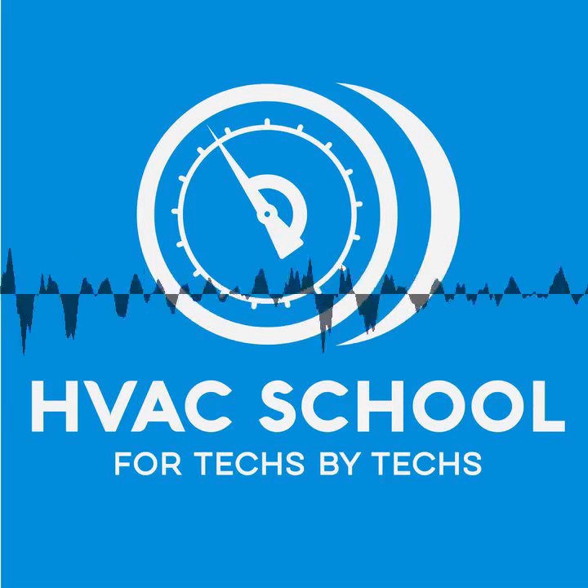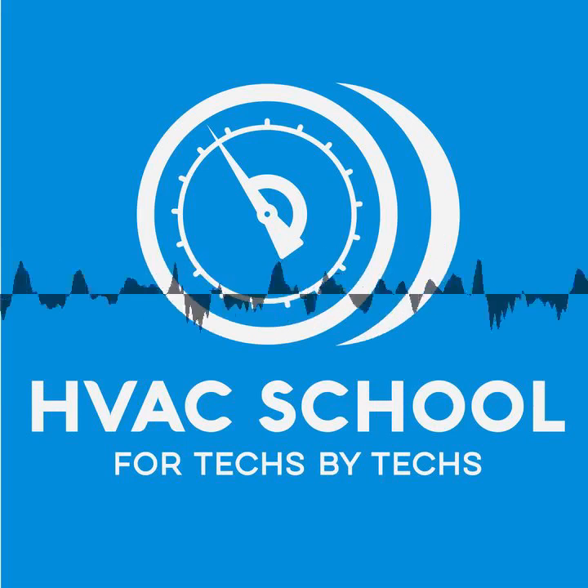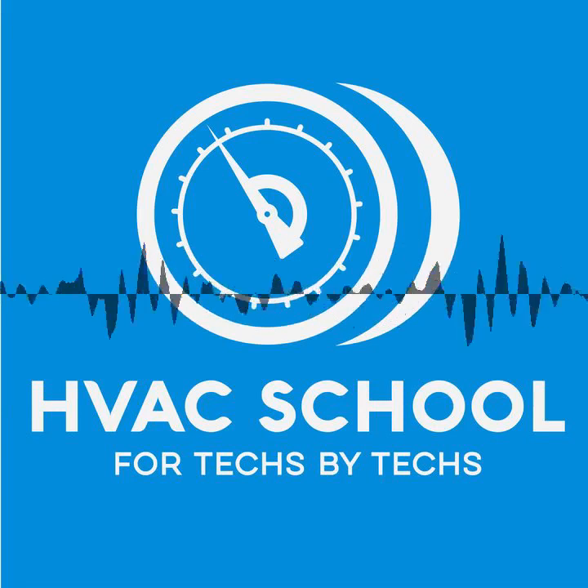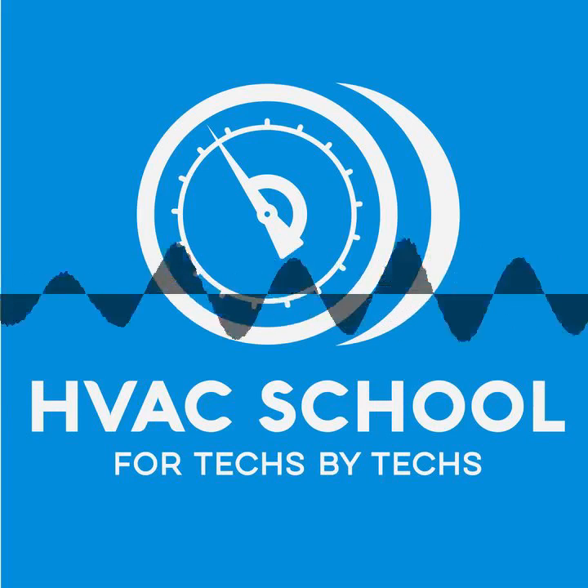If you remember back in the day, the old economizers, I refer to it as the day when you had 3 refrigerants in your truck, right? Generally, the economizer was set up so that it measured the outside air. And there was this range of air conditions outside where if it was the right condition, in other words, it was cool outside with not a lot of humidity, you said, hey, free cooling. So you would bring this air in and you would exhaust the same amount of air outside, or a similar amount of air, depending on whether you want to keep a negative or positive pressure in the building. And this would remove a big chunk of both your latent and sensible load.